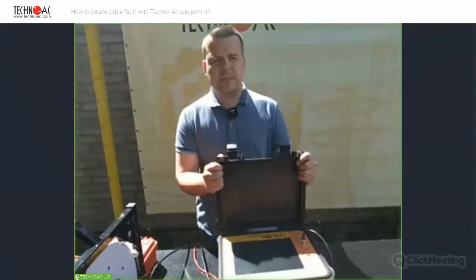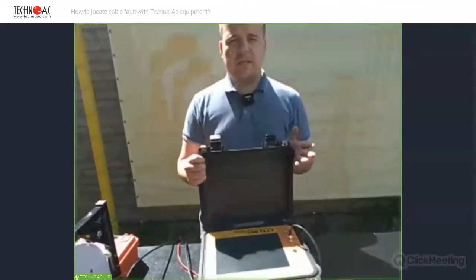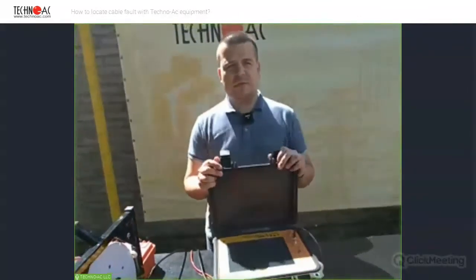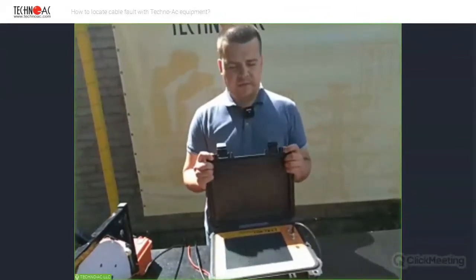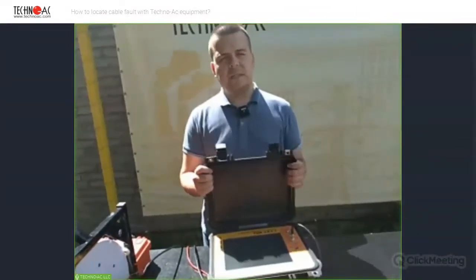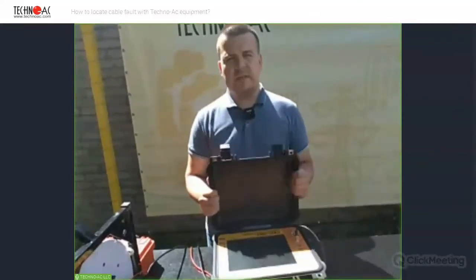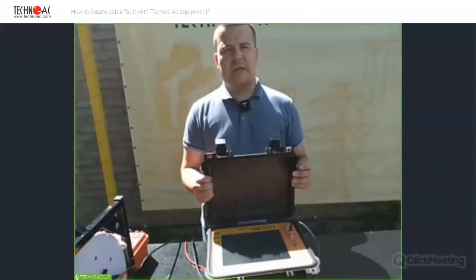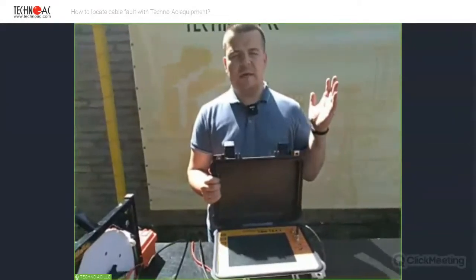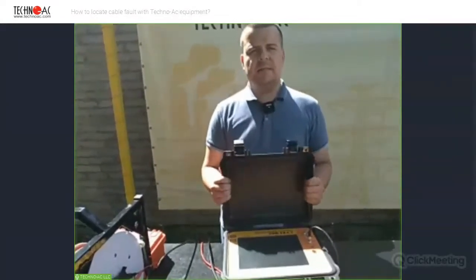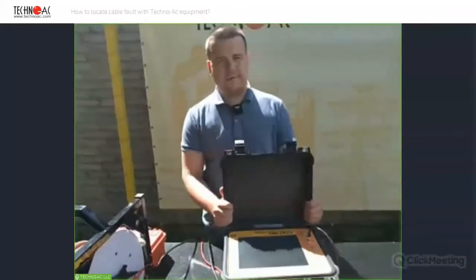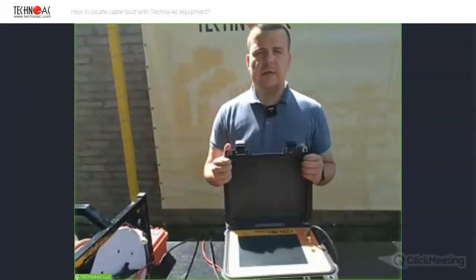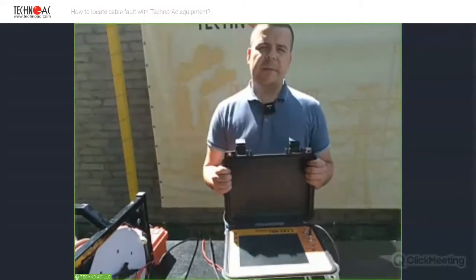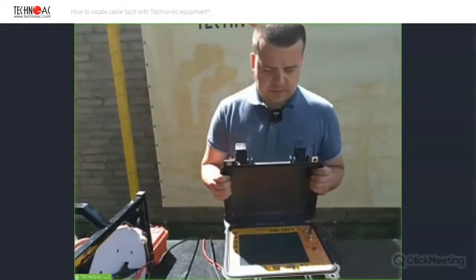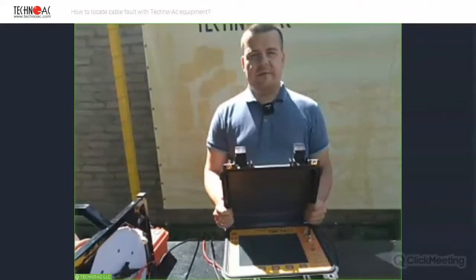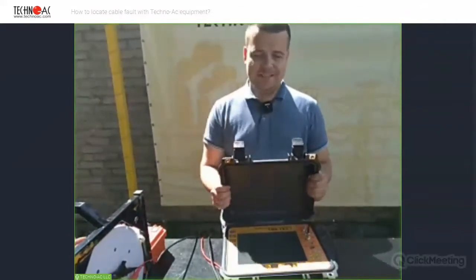The open cut of the cable, the short circuit between two conductors of the cable. Also, this device can detect joints, cable joints. Also it can detect the watering of the cable, and it can detect some other minor faults or minor repairs of the cable, which are not visible by any other device except for your own eyes.